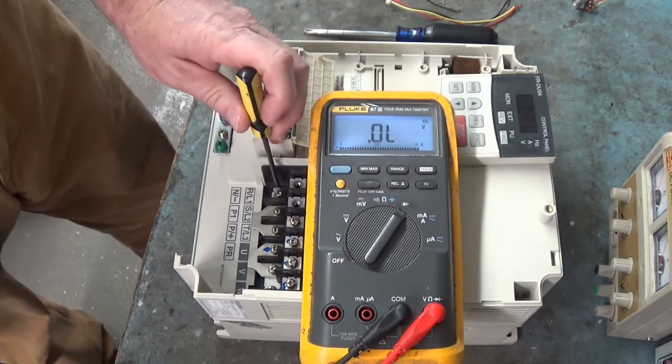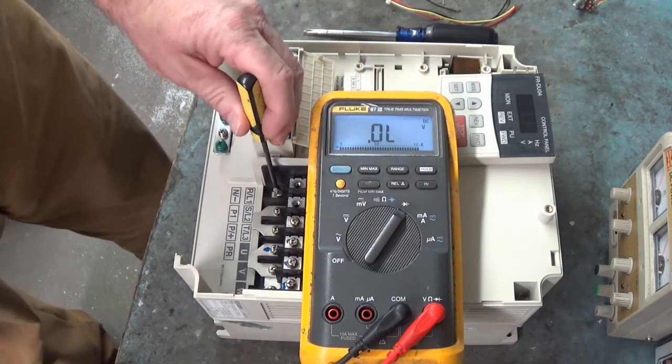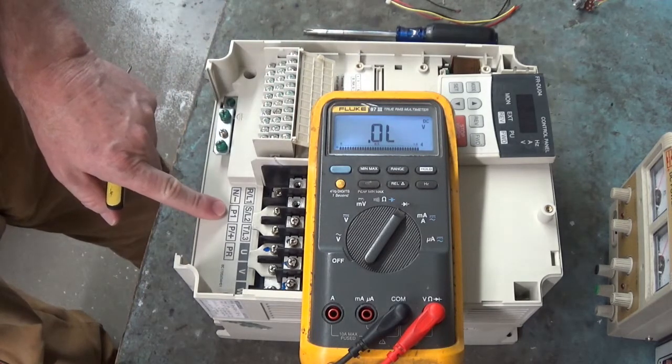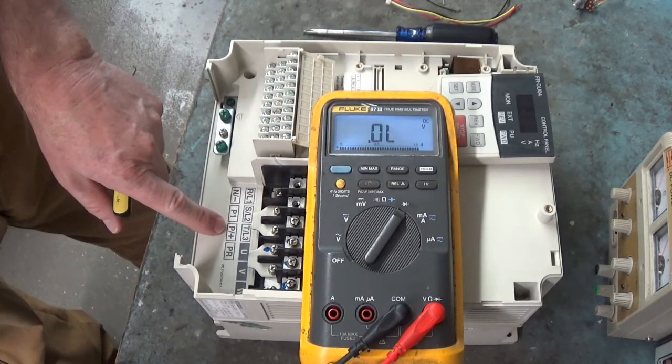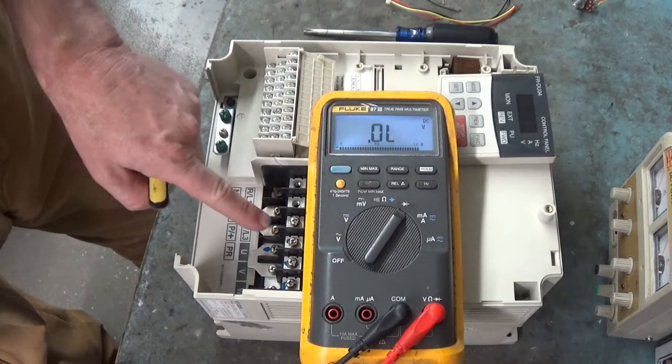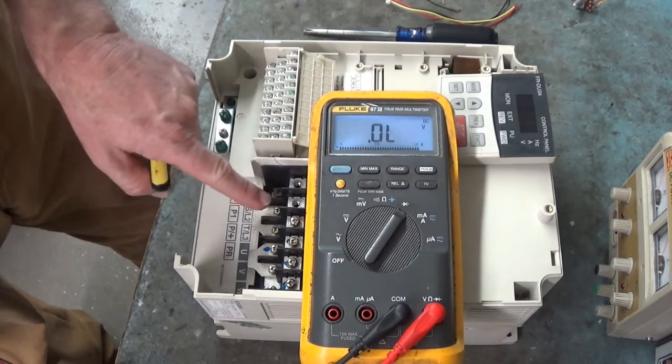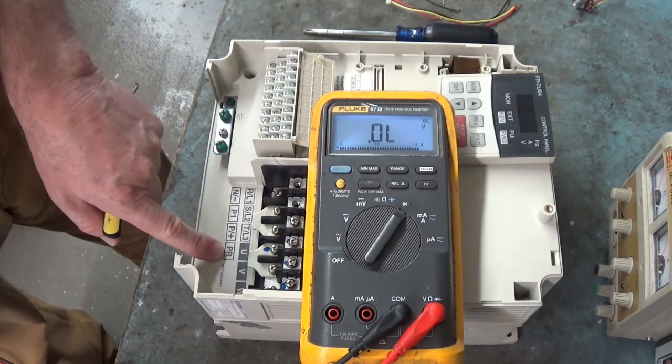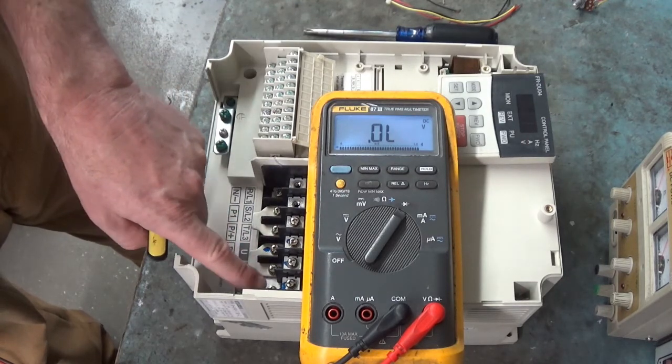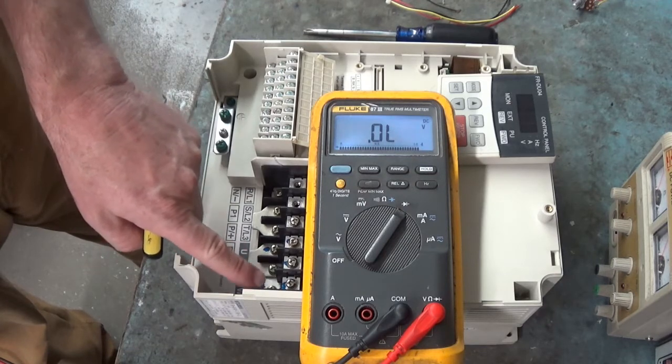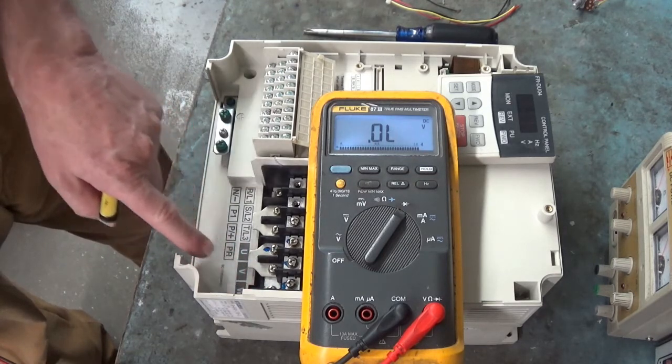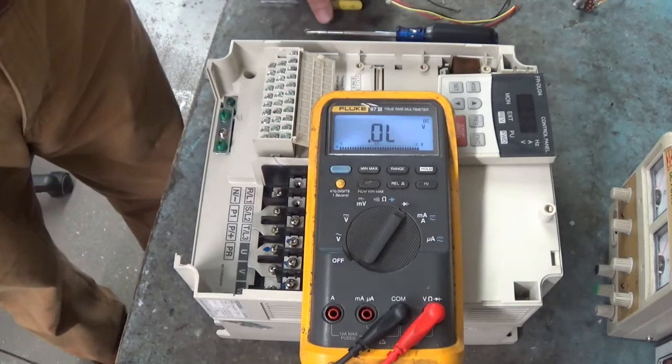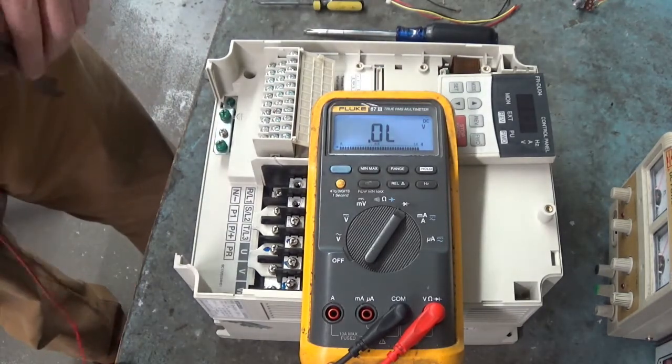Down here is N slash minus. That is bus ground. Here's P1 and P slash plus. They're jumped together with this bus bar right here. This metal tab. And then here's P-R and it's jumped over here. These two N terminals don't go anywhere, but they allow you to connect a regenerative brake and resistor.